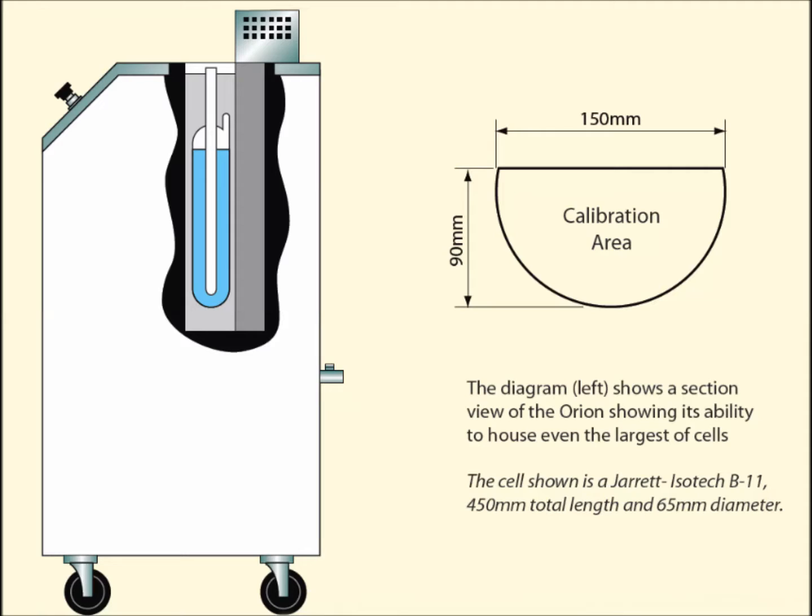This allows the unit to accommodate Isotech's largest water triple point cells, providing a cost-effective sub-millikelvin calibration system.